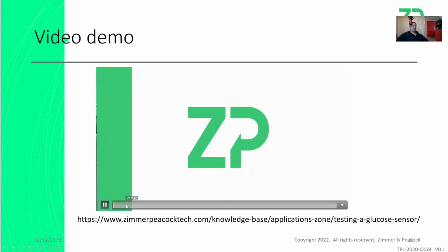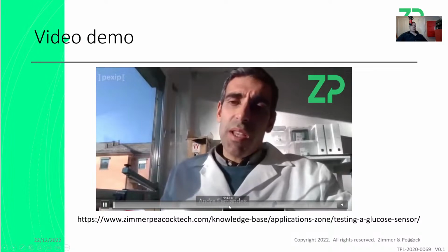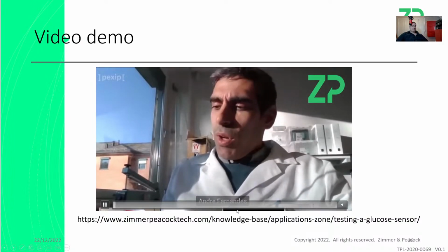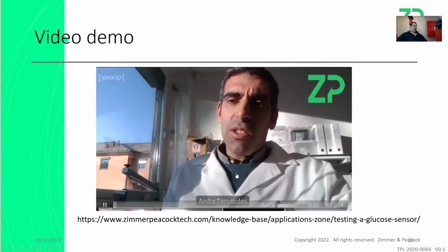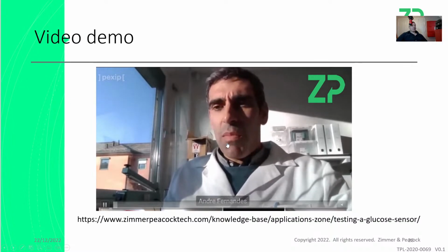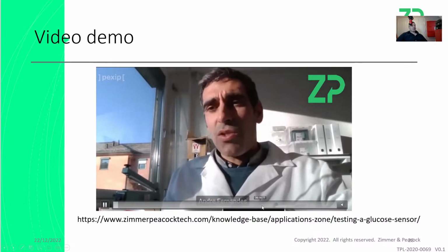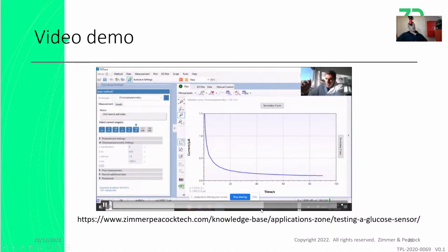This is a famous video, and I laugh because this is one of our engineers called Andre. Andre's obviously still with us, he's been with us for years. A lot of our early videos involve Andre and were filmed with a phone. Again, I'll try to put the link underneath the video. In this video, he shows you how to actually test a glucose sensor. First of all, he's waiting about 100 seconds to get a baseline, and then he's pipetting in.